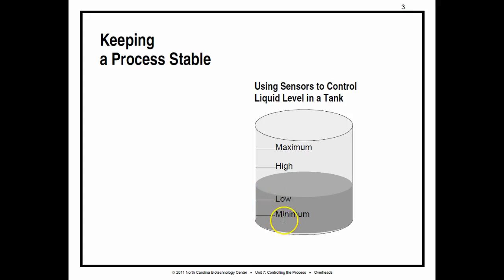It says, hey, you need to go get gas now. I don't know why you've waited this long, but you need to go get gas. Or low could be that point as well. Minimum could be where it's completely empty. Basically, what it's saying is that whenever the liquid reaches the low mark, it tells the control system, hey, start the pump up, refill the tank. And the tank should get all the way to the high point and stop and turn off. And there's usually going to be a little bit of extra that comes out through. And that's why there's a difference between a high and a maximum. Maximum is the most amount it can hold.